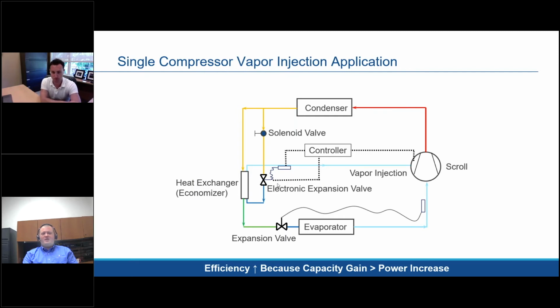That's going to go through typically an electronic expansion valve because it's going to have to be able to open and shut, more to a wide variety of mass flows. Typically, we're trying to control that, 7 to 10 degrees superheat for vapor injection. That's going to go through a heat exchanger to help make sure that that gas flashes when it goes back into the scroll itself. And that's where you start getting your drastic increase in capacity because you're bringing this extra vapor, and it's warmer vapor than what it would be if it would go all the way through the evaporator and cool down from the outside. So you're increasing that mass flow. The compressor's built-in volume ratio at that point is getting larger, which allows you to move more refrigerant into the condenser in order to get more heating capacity.